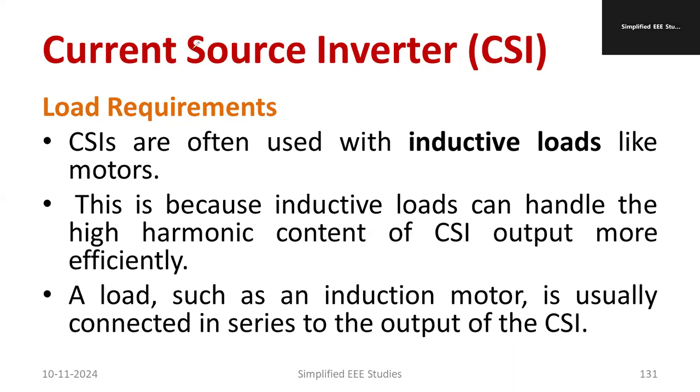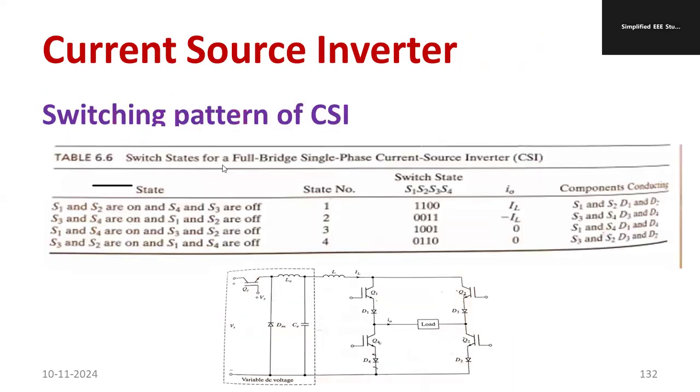What kind of load are you going to use for current source inverter? Major application is inductive loads, especially motors. Heavy inductive loads can handle harmonics effectively. It can handle the harmonic efficiently. If you are using highly inductive load, you can use CSI. But for loads like lighting load, harmonic content is not advisable.